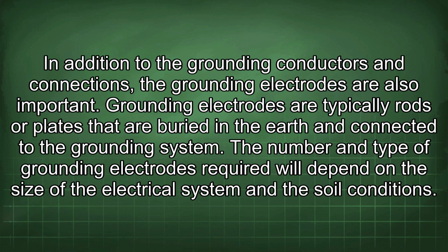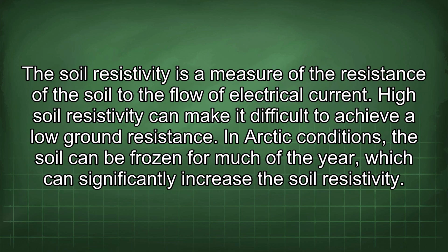In addition to the grounding conductors and connections, the grounding electrodes are also important. Grounding electrodes are typically rods or plates that are buried in the earth and connected to the grounding system. The number and type of grounding electrodes required will depend on the size of the electrical system and the soil conditions. The soil resistivity is a measure of the resistance of the soil to the flow of electrical current. High soil resistivity can make it difficult to achieve a low ground resistance. In Arctic conditions, the soil can be frozen for much of the year, which can significantly increase the soil resistivity.